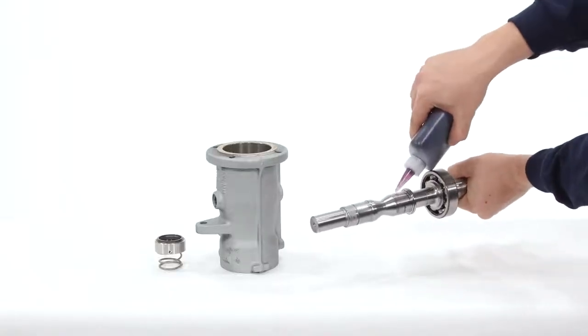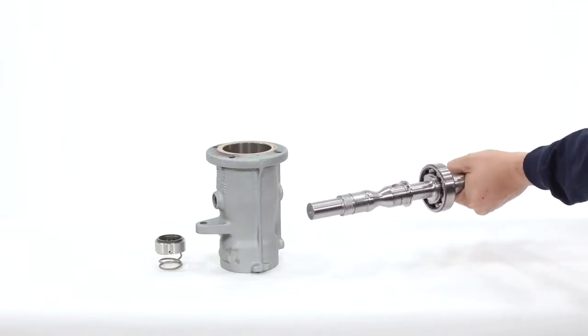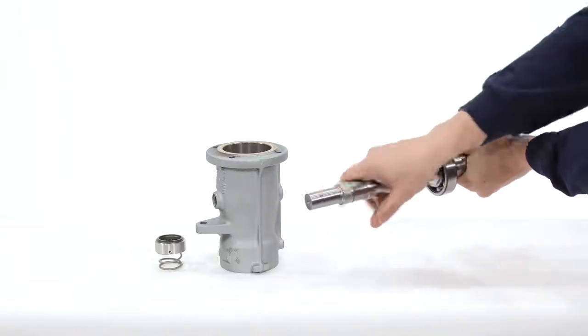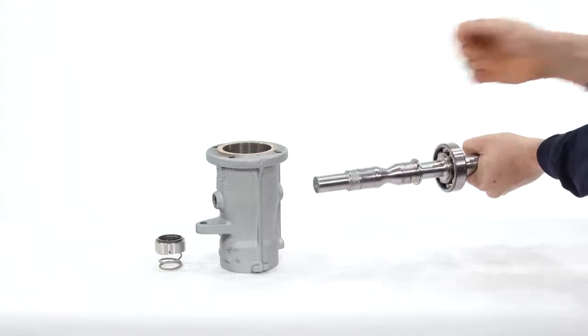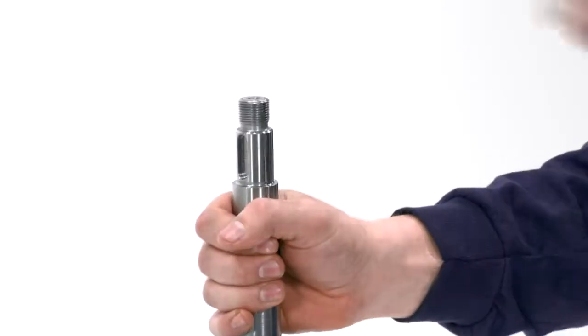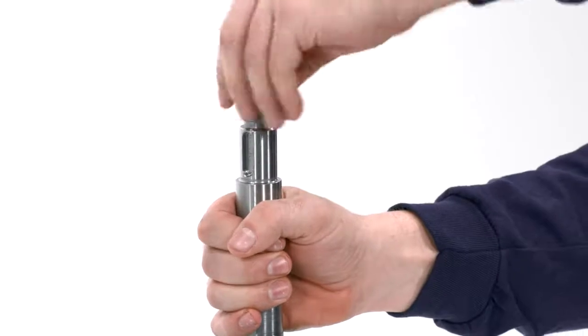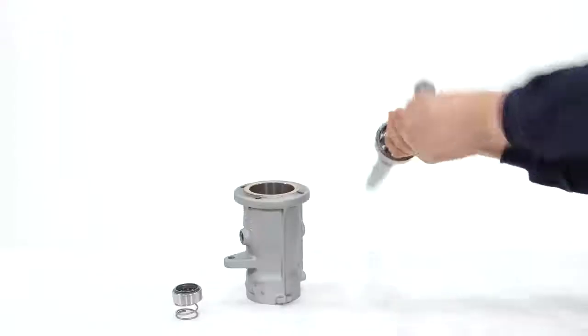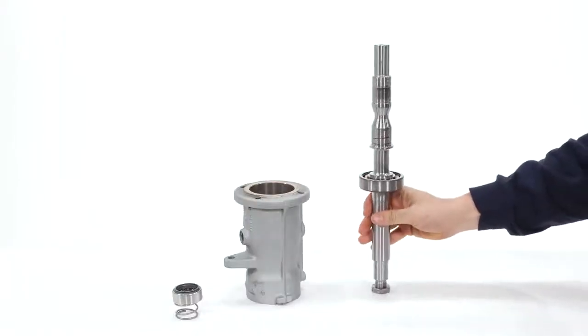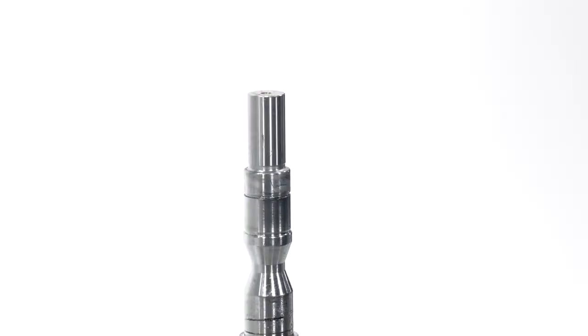Lubricate the shaft to aid the installation of the rotating face of the mechanical seal. You may want to add the nut to protect the threads of the shaft. Install the rotating face of the mechanical seal onto the pump drive shaft.